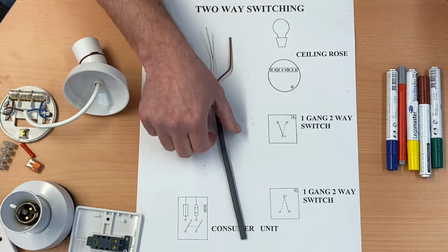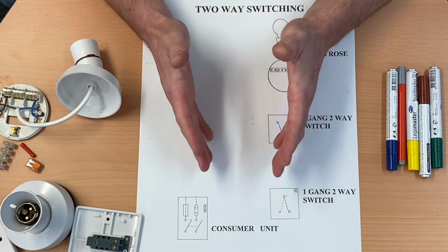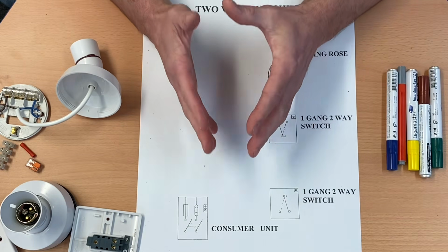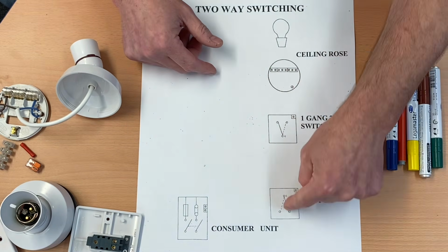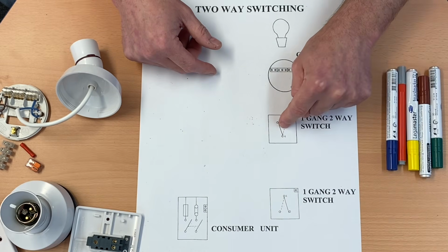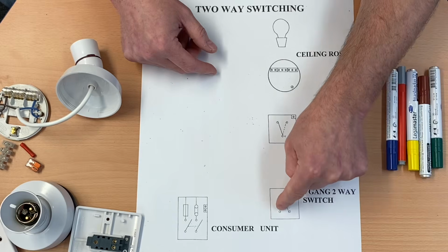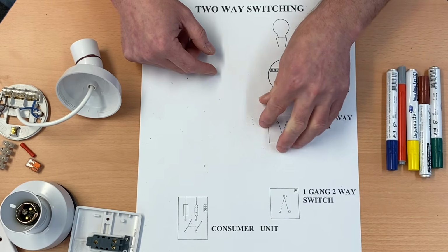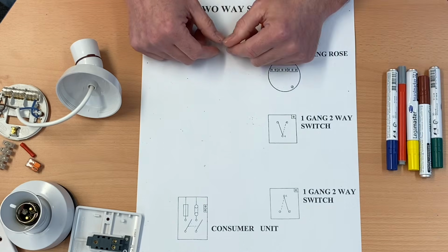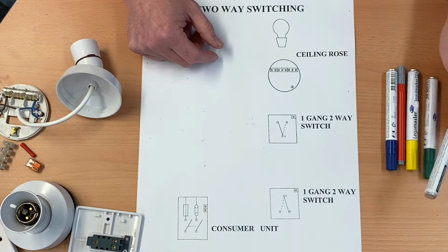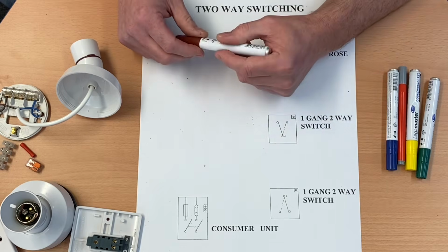So let's do the first part, which I said was identical to when we did our one-way lighting circuit. If you've got a one-way lighting circuit in a room, you can easily turn it into a two-way lighting circuit by simply adding one more cable between the switches. So if you had a switch at the door and you wanted to put a switch somewhere else in a bedroom, you just put a 3-core cable between the two and change the original one-gang one-way switch for a two-way switch. That links in with the first video we looked at. Remember, I'd expect you to be using a ruler. I'm doing it upside down, and obviously I'm doing it freehand, but I'd expect you to use a ruler.